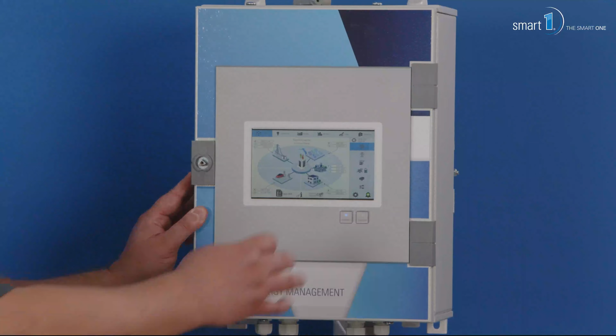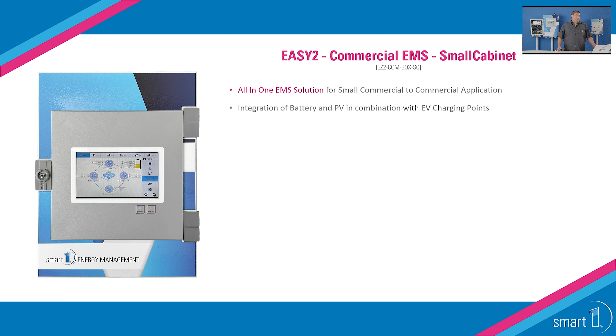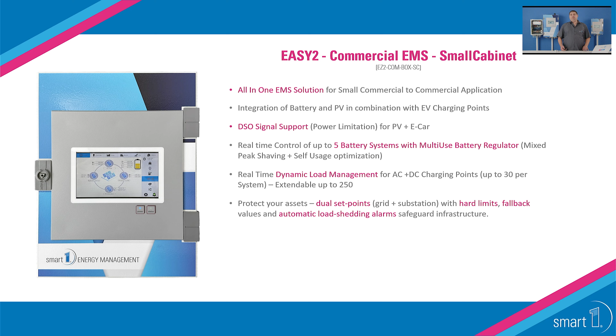So it's an all-in-one solution for small-scale commercial applications, like I just told you. It has integration for battery, PV, and also AC and DC EV charging points. We have the DSO signal support for PV and the e-car. We have real-time control for up to 5 battery systems in a multi-use battery concept, for example with mixed peak shaving and self-usage optimization. We have real-time dynamic load management for AC and DC charging points. It also protects your asset with the dual set point concept that we had before, but we will see in this project that it's actually being used. And it's an all-in-one rugged wall cabinet. It ships pre-wired with a display controller, with a 5-port Ethernet switch, with a 24-volt power supply, and it's designed for plug-and-play deployment. And again, we also provide online commissioning support from SmartOne and also from partners for those kinds of projects.